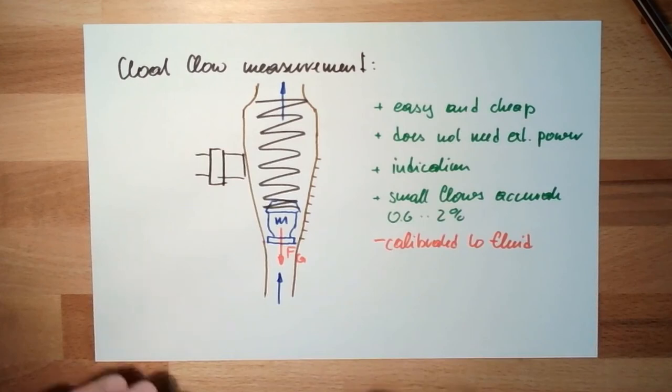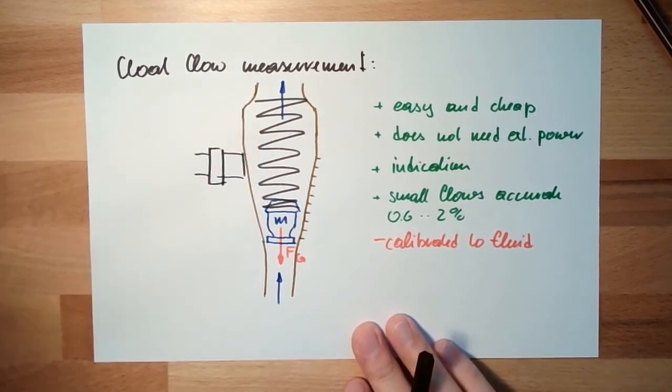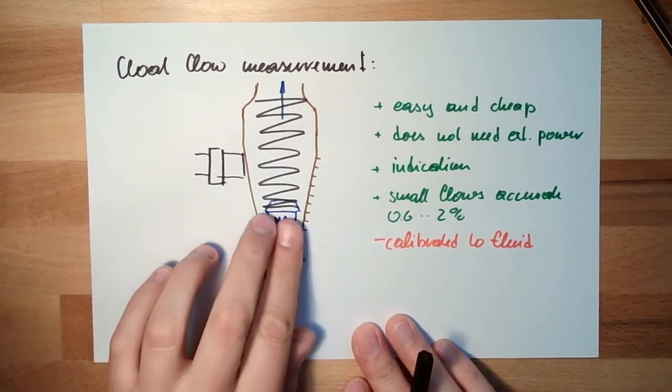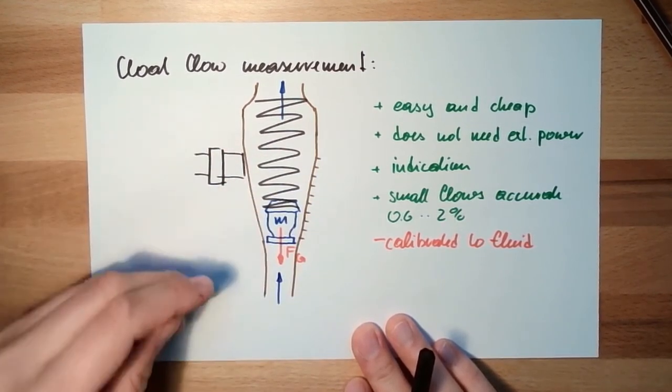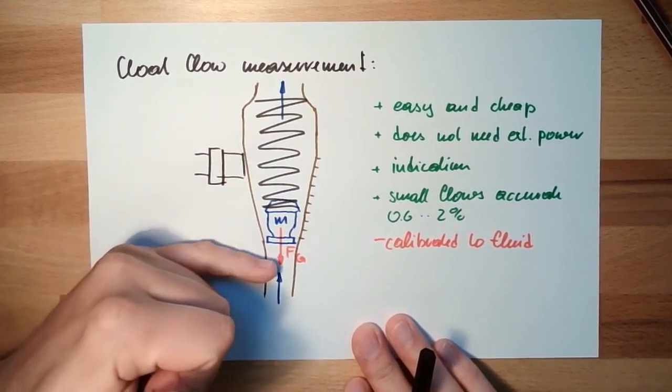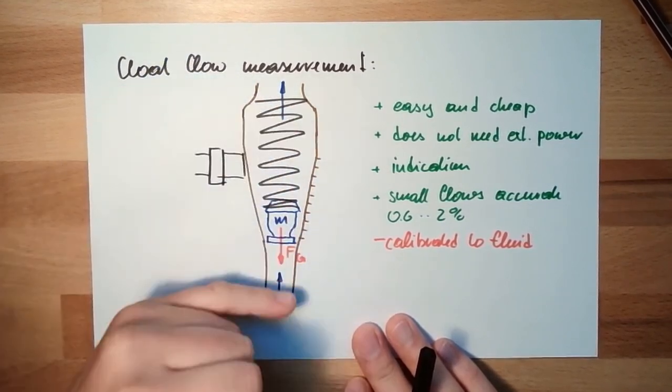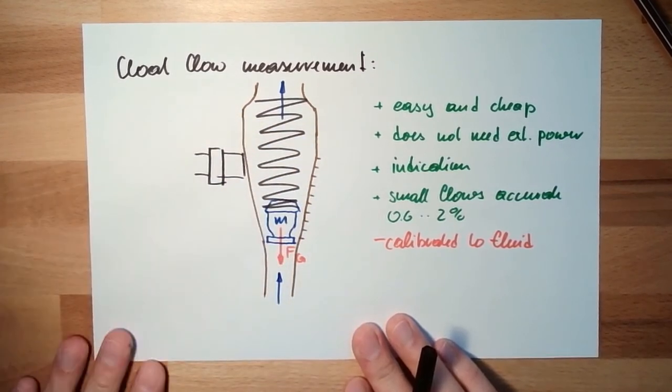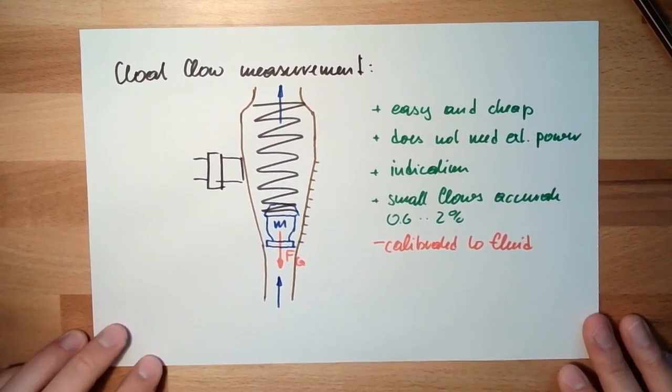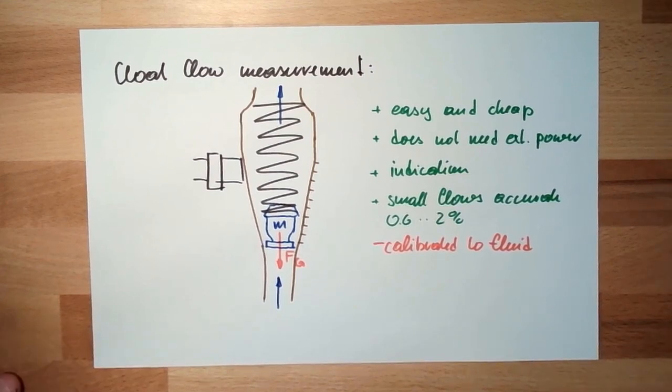It's also possible to have a switch - inductive switch, capacitive switch. When the float passes, the switch is activated to watch if there is enough cooling water running through. If the float goes down, the switch will indicate there's not enough cooling liquid flow.